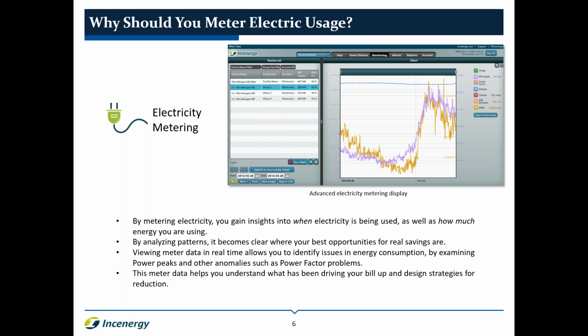We want to have the ability to measure not only what energy is being used, but when it's being used, how much energy at any particular time. We want to examine these patterns, to see if there's energy being consumed outside of the normal operating hours, or if there's an anomaly where peak power is being reached at certain times of the day so we can reduce the peaks. We want to examine the quality of the power and see if there's a way we can improve that quality and save money. So this metering capability gives you that visibility and allows you to reduce your consumption and reduce your cost.